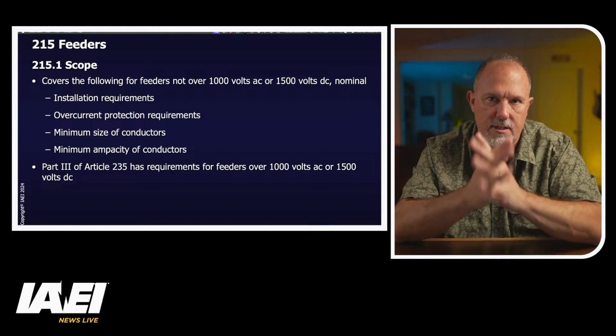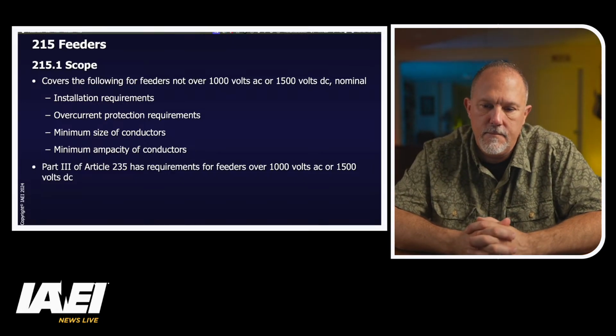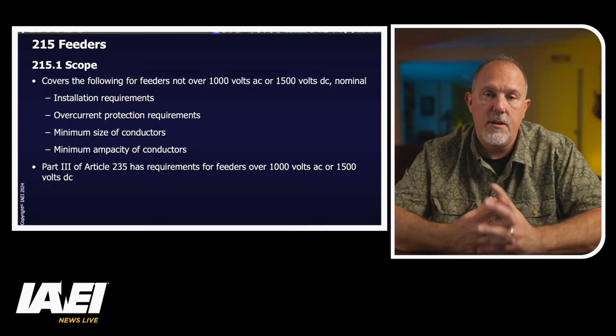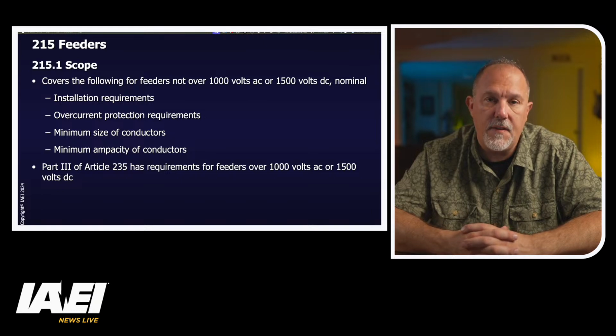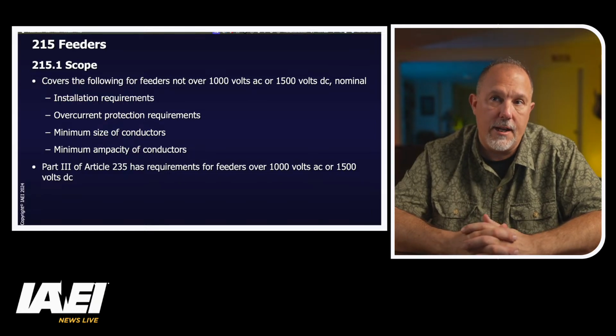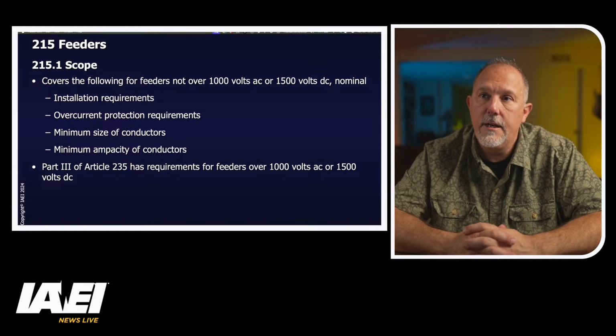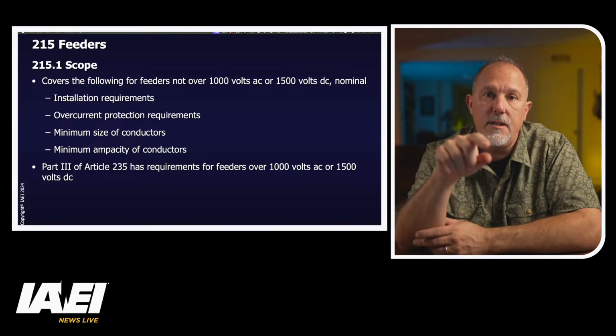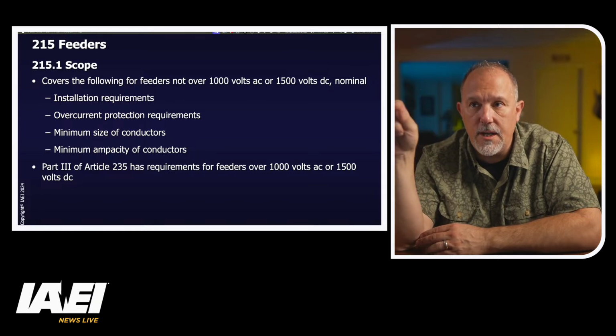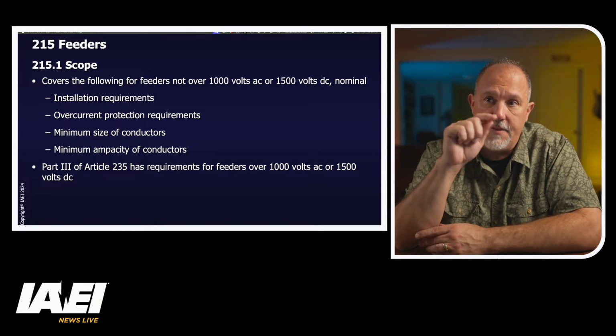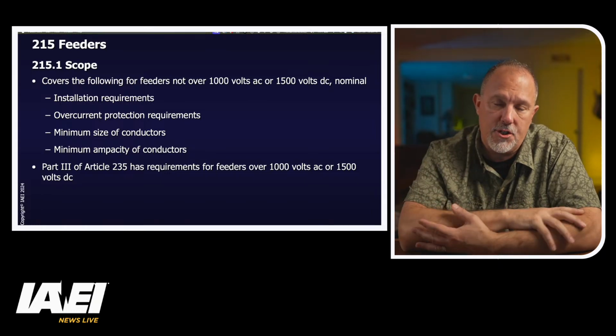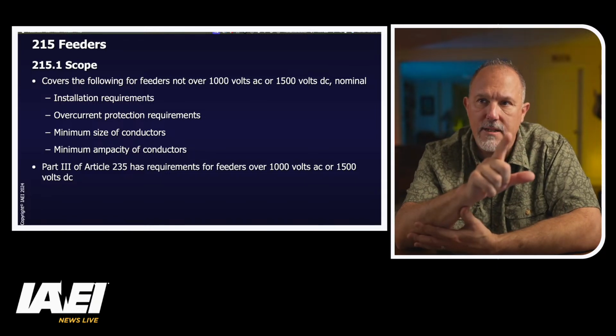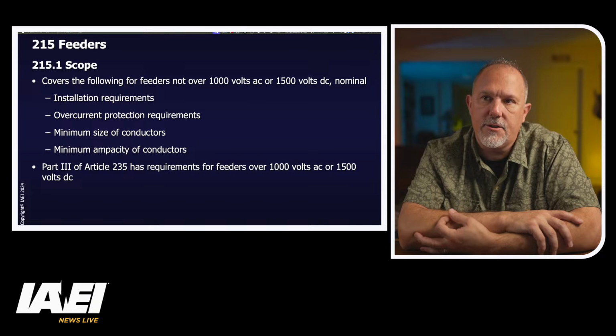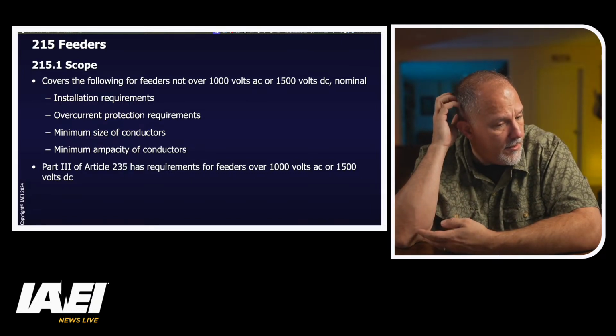So just keep in mind, the moment you get into a code panel's purview, we have different terminology. And we have to think about that from the perspective of when you're in and when you're not in Article 215. Now, the scope of 215 covers feeders not over 1,000 volts AC or 1,500 volts DC. Keep in mind, in the 2023 code, it's Part 3 of Article 235 that addresses the medium voltage feeder application requirements. So we're going to be looking at installation, overcurrent protection, minimum size of conductors, and the minimum ampacity of conductors. All right, does that make sense?